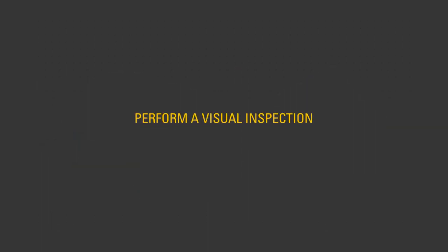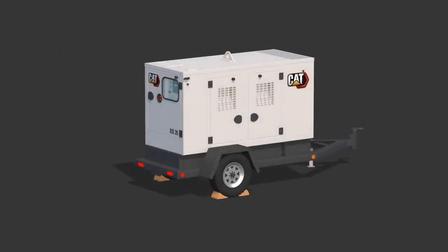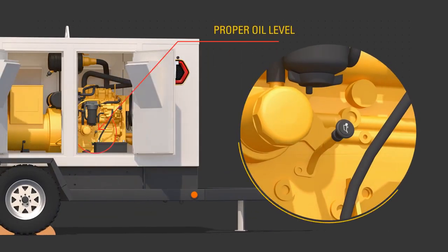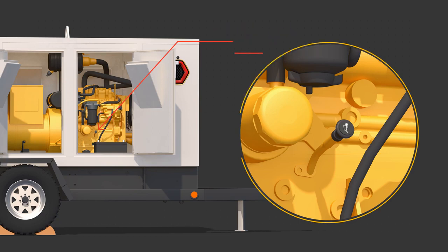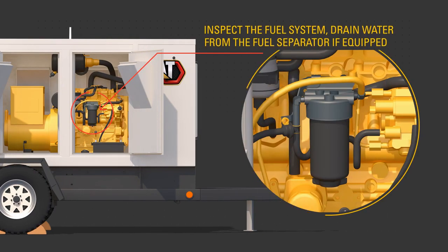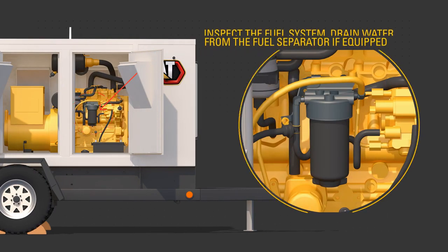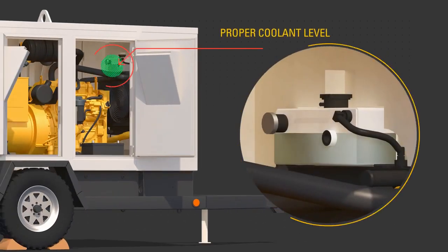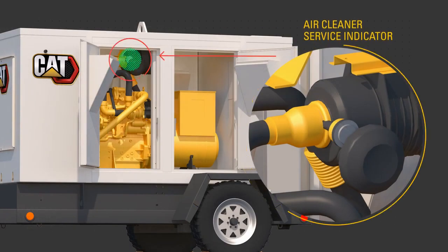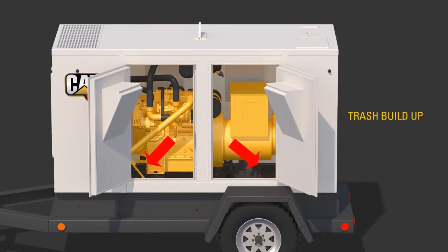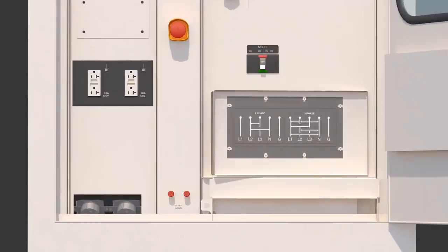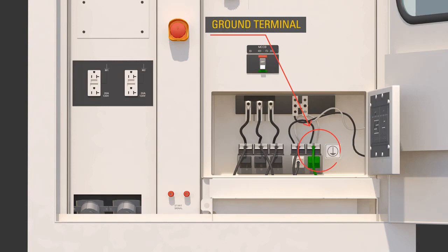Perform a visual inspection of the unit. Look for proper oil level, proper fuel level. Inspect the fuel system. Drain water from the fuel separator if equipped. Proper coolant level. Check the air cleaner service indicator. Trash buildup in the engine compartment. In addition, make sure that the ground terminal is properly connected according to site requirements.